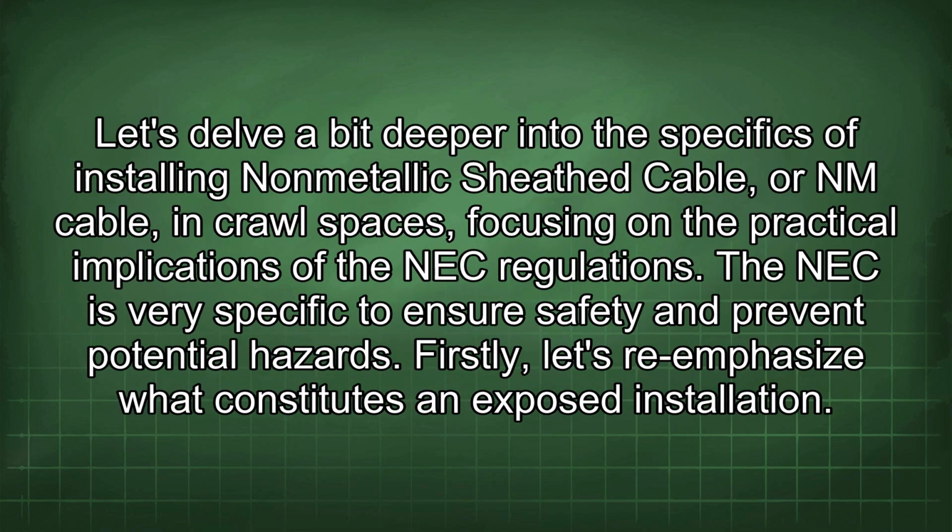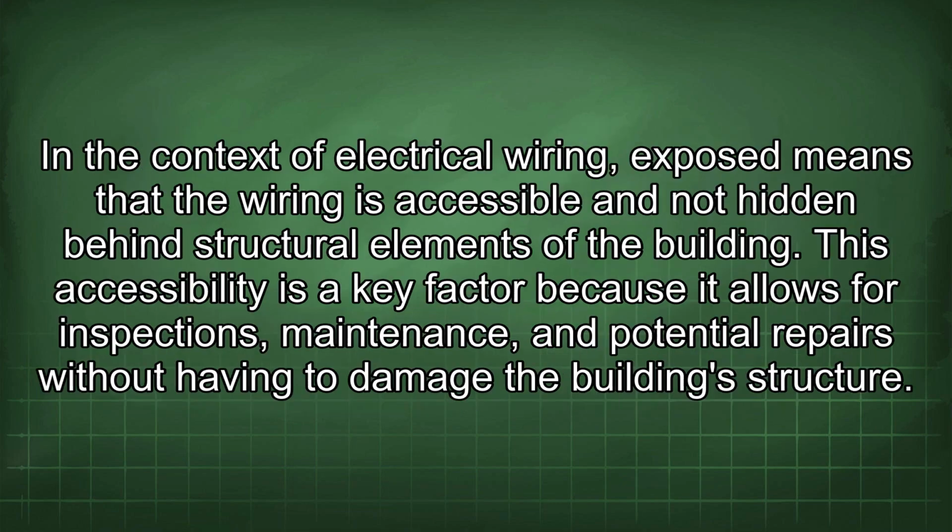Let's delve a bit deeper into the specifics of installing non-metallic sheath cable, or NM cable, in crawl spaces, focusing on the practical implications of the NEC regulations. The NEC is very specific to ensure safety and prevent potential hazards. Firstly, let's re-emphasize what constitutes an exposed installation. In the context of electrical wiring, exposed means that the wiring is accessible and not hidden behind structural elements of the building.